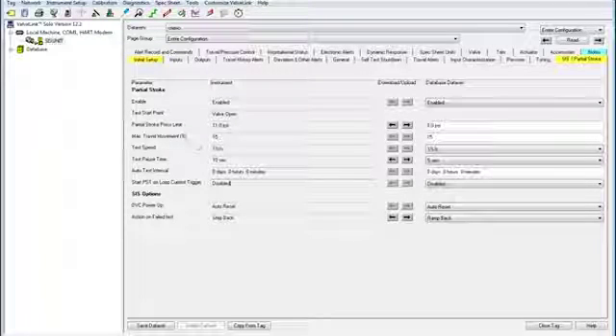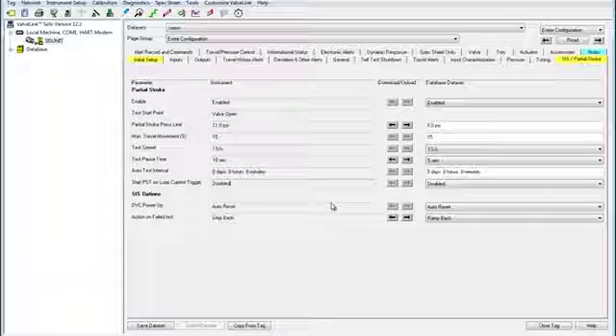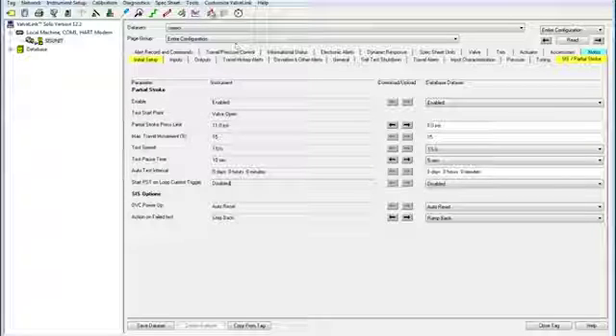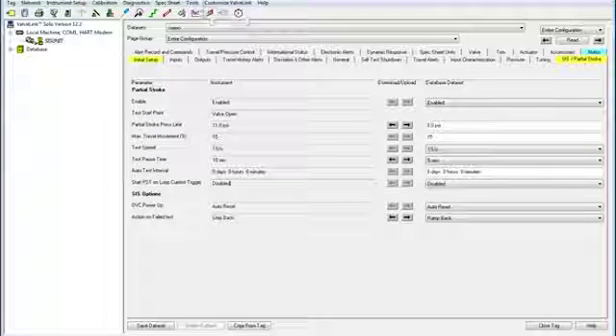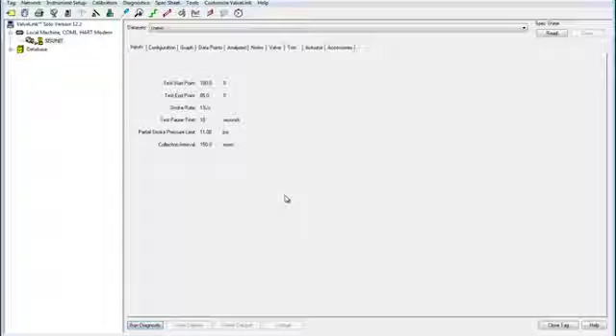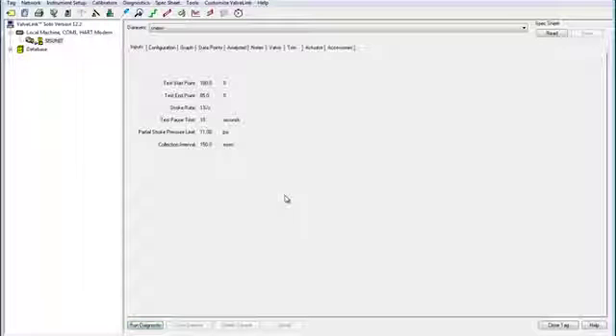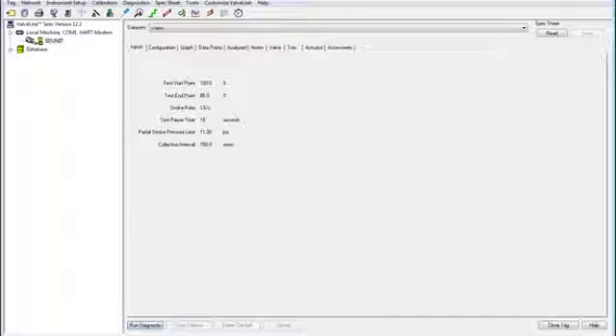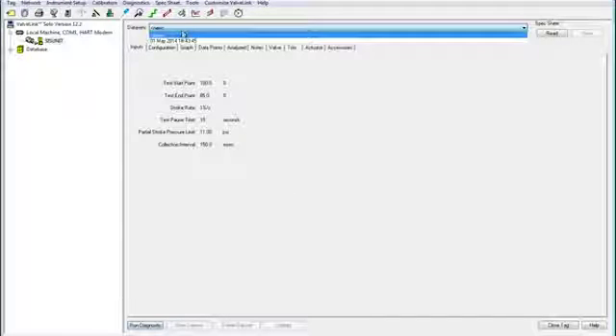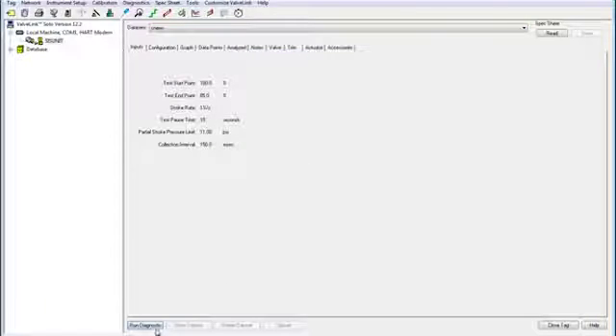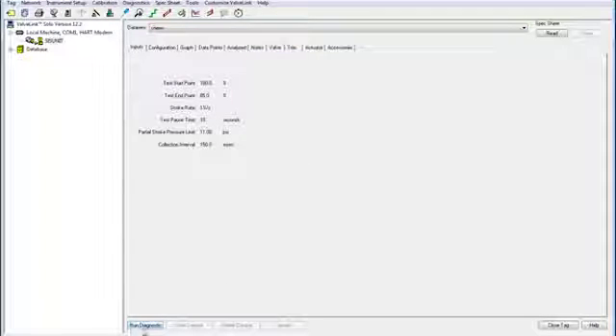Now we're going to run the partial stroke test. Go up here and click this partial stroke test icon. This button pulls up the SIS diagnostics with this window. Make sure you have a new data set selected, and then click run diagnostic. This will move the valve and perform the partial stroke test.